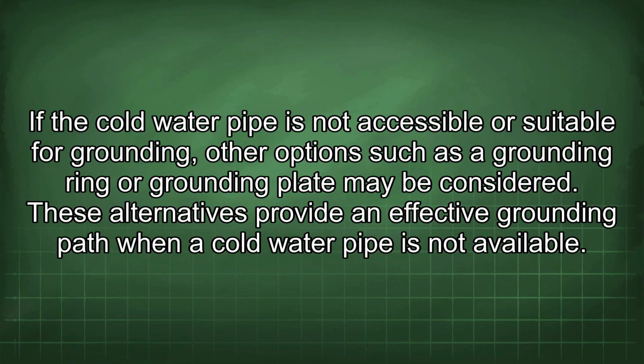If the cold water pipe is not accessible or suitable for grounding, other options such as a grounding ring or grounding plate may be considered. These alternatives provide an effective grounding path when a cold water pipe is not available.